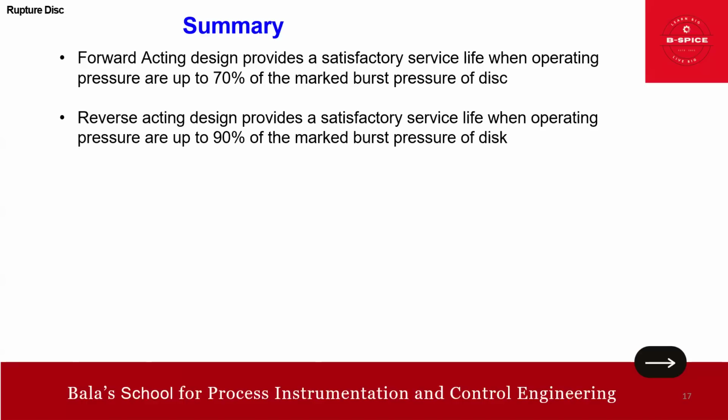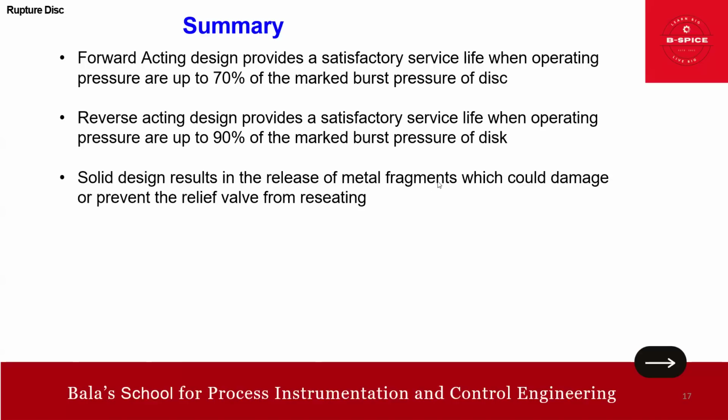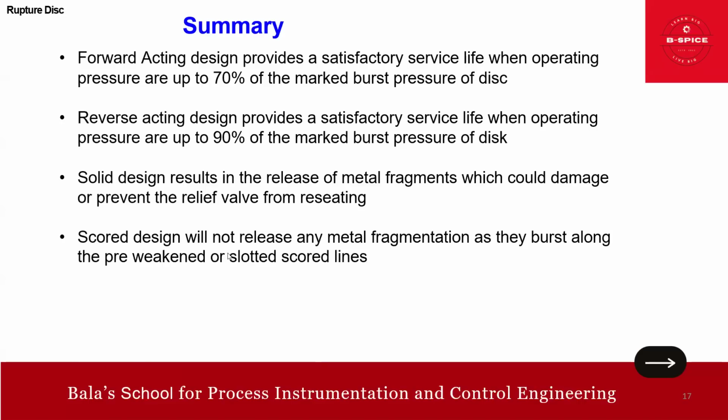This is just a performance rating. Solid design results in release of metal fragments, which could damage or prevent the relief valve from reseating, so we need to avoid this. Score design will not release any metal fragments, as it bursts along the pre-weakened or slotted score lines.